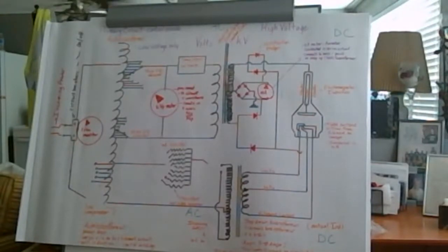If we don't have any type of voltage compensation in our equipment, this would cause very different X-rays to be produced at different times. Anytime there was a decrease in the incoming power, our X-rays would appear underexposed, and anytime there was an increase in power, we could have overexposed X-rays.